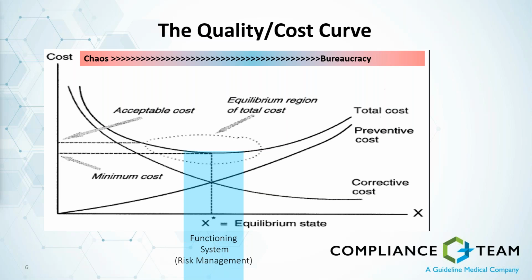And then the next question that you asked was about how much information I should provide in the CAPA. The amount of information that should be provided is enough that you get to what the actual problem is. You define that problem succinctly, and anything beyond that might be excessive. Again, we want to keep things focused on impact.